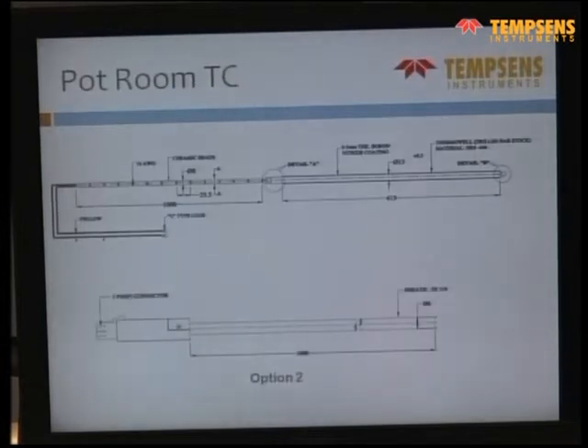In the case of the pot room, they are using a 446 tube with boron nitride coating, and the thermocouple is bare wire or an MI cable, and you can see the tip at the bottom. They are pushing it inside the molten aluminium to take the temperature, and you can get maybe 30 to 70 dips of the pot temperature. Another option is using high wall thickness MI cable, in SS304, and this is also for the same application of pot room temperature measurement in the aluminum plant.